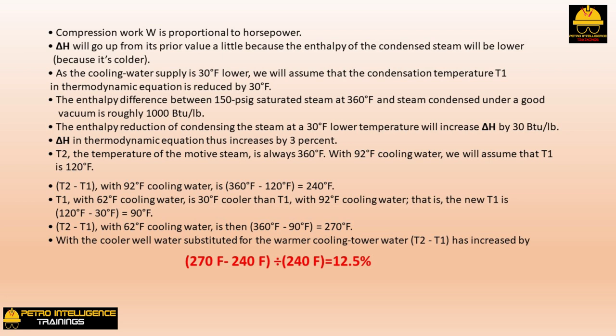Using the thermodynamic equation, compression work W is proportional to horsepower. ΔH will go up a little because the enthalpy of the condensed steam will be lower as the cooling water supply is 30°F lower. We assume that the condensation temperature T1 is reduced by 30°F. The enthalpy difference between 150 psig saturated steam at 360°F and steam condensed under a good vacuum is roughly 1,000 BTU/lb. Condensing the steam at 30°F lower temperature increases ΔH by 30 BTU/lb — a 3% increase.